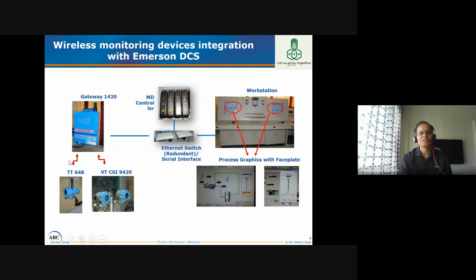So wireless monitoring devices integration, how does it happen? You can see here devices, gateways, then it is on Ethernet. So an Ethernet switch is there, and this Ethernet switch is for networking purposes. In one of the ports you connect the gateway. One port goes to the DCS controller. Two ports go to the workstations, like these two workstations here. Workstation means PCs for graphic display.